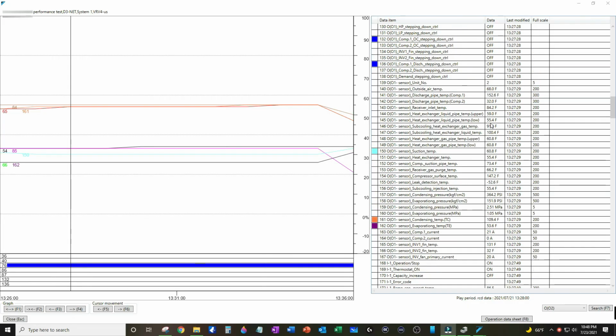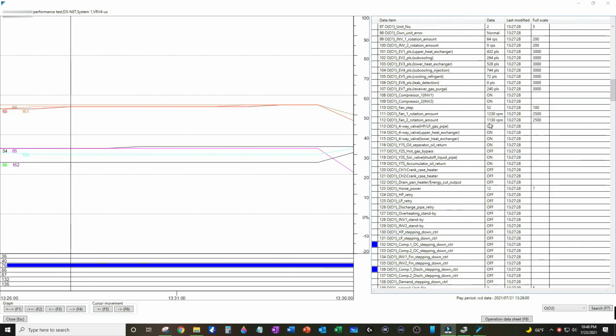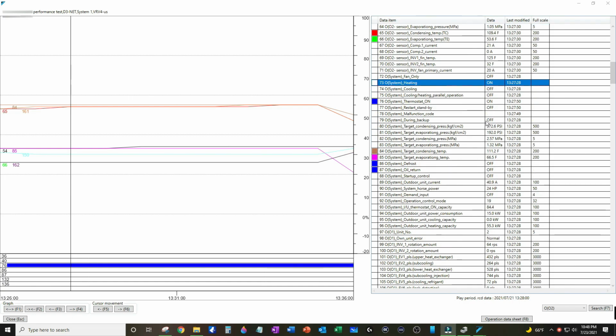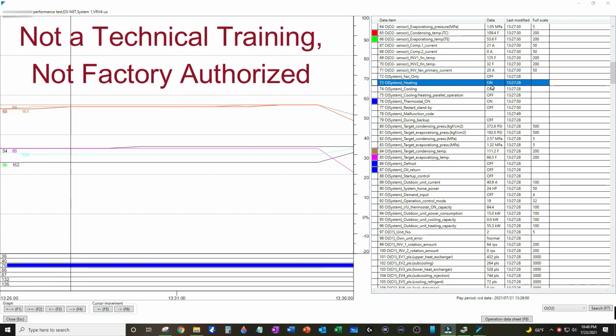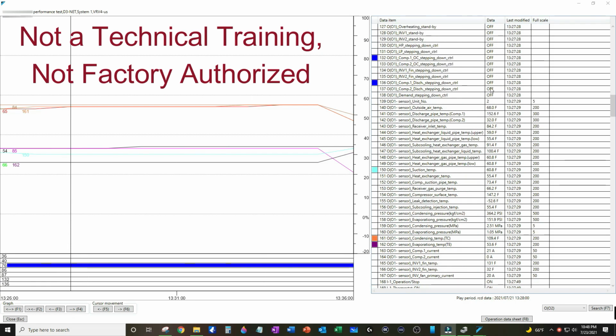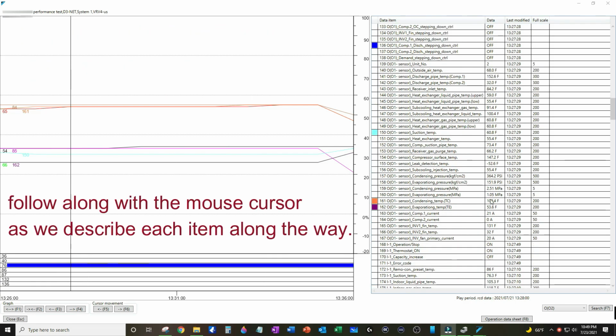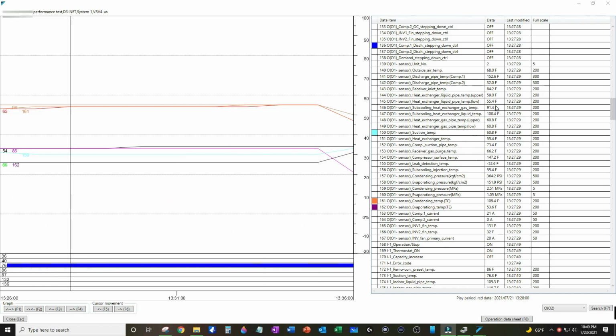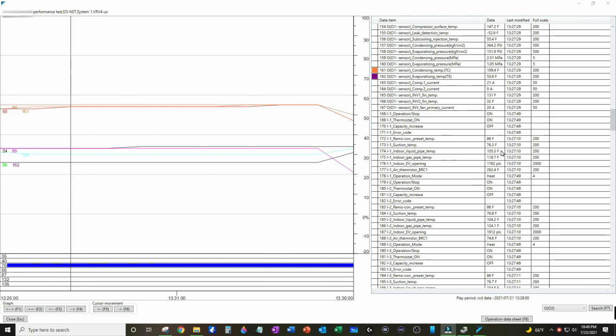In the heat mode, I'm going to be looking at a lot of stuff here, about 2 days worth of training type stuff actually. So again, I remind you, this is not a technical training, more just a narrative to bring you all along for the ride. I checked the discharge superheat. It's a little low, but within normal range. I then quickly check my outdoor heat exchanger temperature to make sure my four-way valves aren't sticking at all and letting hot gas into the outdoor coil. This would be bad for heat mode.